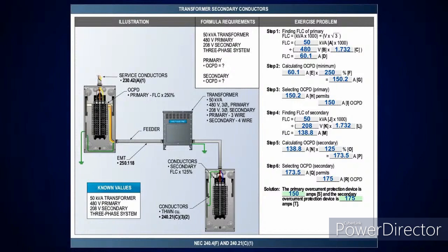So I'll take the 50 kVA times 1,000, which is 50,000, divided by the primary voltage, which is 480 volt 3-phase, or 831 volts, and that gives you 60.1 amps. Then I take that at 250%, which gives me 150.2. I drop down to the next standard size in table 240.6(A), which is a 150 amp overcurrent device.